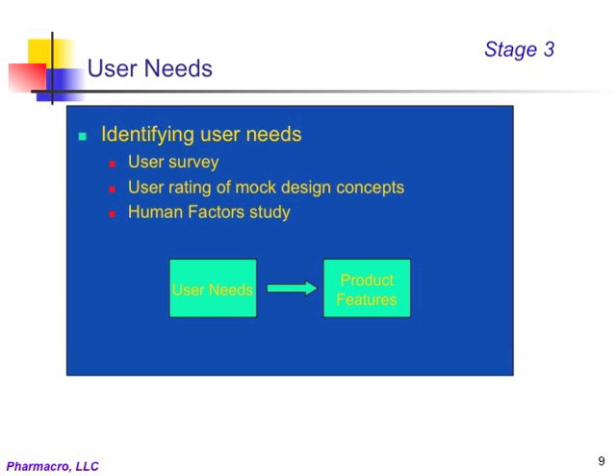The device has to be designed in such a way that the probability of making an error during use is minimized. For example, if the device has an LCD display and it has several buttons that change the content of the display, then human factor studies will involve trials with potential users to determine the optimum combination of display and pushes of buttons that will convey the intended information on the display as unambiguously as possible. This finding would then be converted into requirements for the software that will be developed for the display.